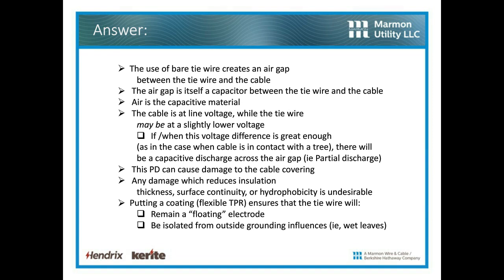This PD can cause damage to the cable covering. Any damage which reduces the insulation thickness, surface continuity, hydrophobicity, integrity, etc., is going to be undesirable. So putting a coating on that tie wire, whether that's a flexible thermoplastic rubber, ensures that it will remain a floating electrode and be isolated from outside grounding influences, you know, if we're in contact, say, with wet leaves.